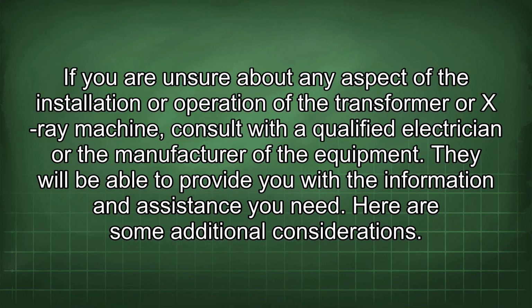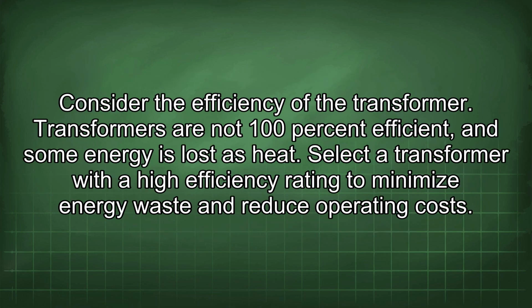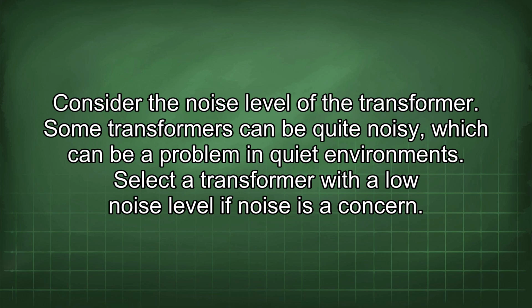Here are some additional considerations. Consider the efficiency of the transformer. Transformers are not 100% efficient, and some energy is lost as heat. Select a transformer with a high efficiency rating to minimize energy waste and reduce operating costs. Consider the noise level of the transformer. Some transformers can be quite noisy, which can be a problem in quiet environments. Select a transformer with a low noise level if noise is a concern.